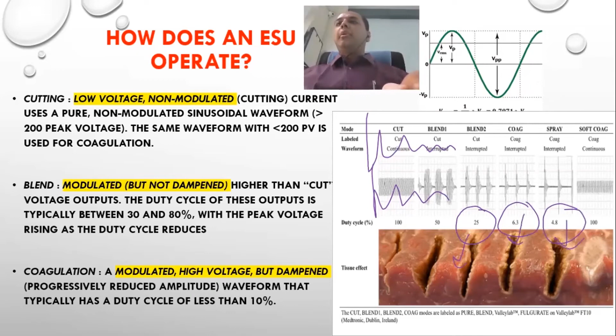So we must go through the manual of the manufacturer to see the displayed pure monopolar cutting mode in this machine. It operates at a maximum of 400 watt at 300 ohm resistance. It gives information about the waveform, peak voltage, crest factor, and crest factor is directly proportionate to the ability of the machine to coagulate. All ESUs can track an impedance baseline and subsequent changes in the impedance.